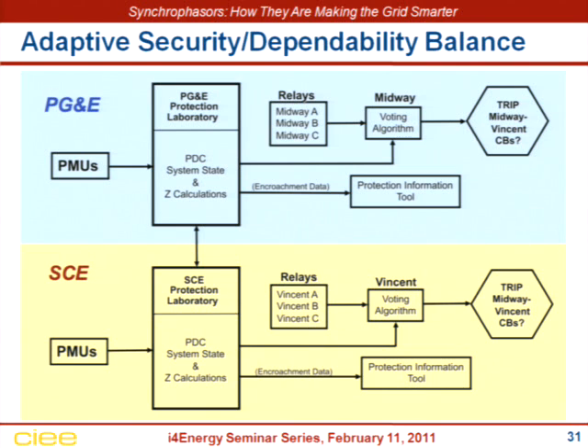Now the problem becomes that any one of these relays can trip the line. The other 2 may not see it, but one does. And if one does, and all lines are in service and there's no stress in the system, you can survive a trip of one line. The system is designed to be able to tolerate a trip of a single line with everything else being fine. That's the extra margin that's always been built into the system. Again, for reliability and dependability.